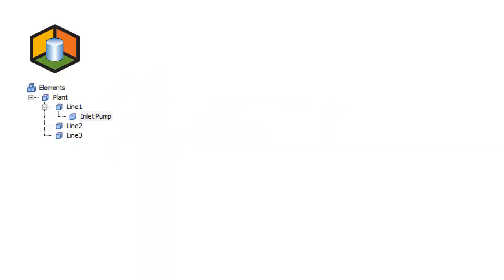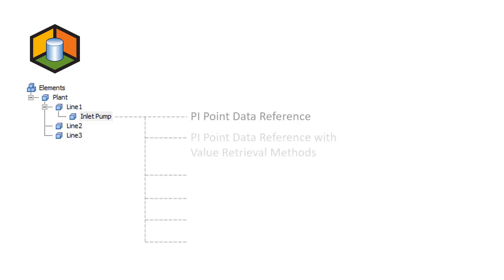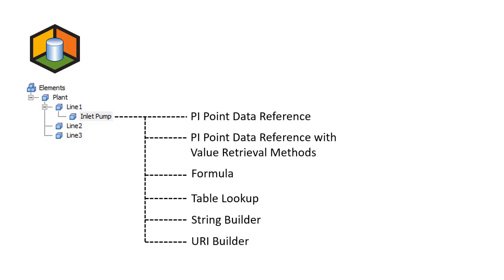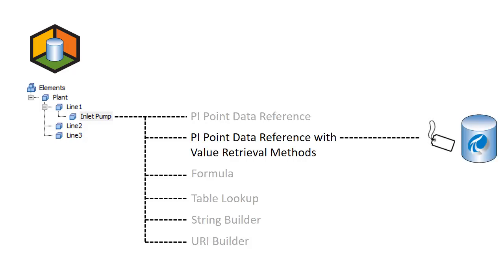Data references are used to associate various items to attributes in your AF hierarchy. In the case of PI Point data references, we have the option to add value retrieval methods. Value retrieval methods change the type of requests for data made to the PI Data archive, based on the time context of the client. Before hopping onto PI System Explorer to configure a PI Point data reference with a value retrieval method, let's explore what's meant by the client time context.